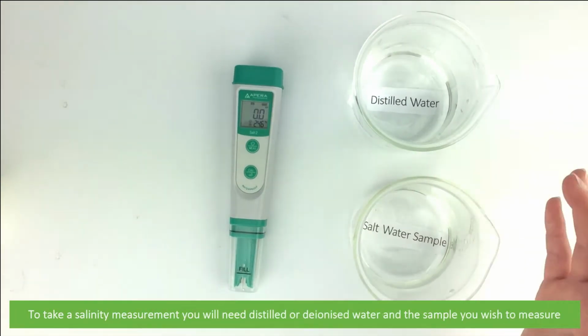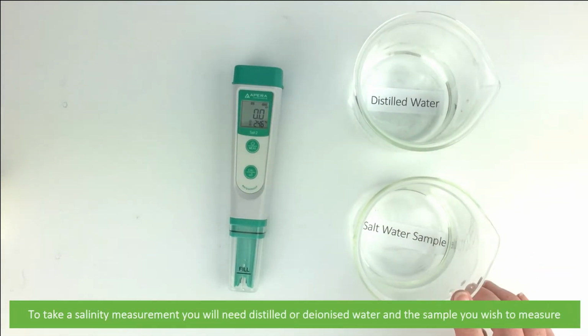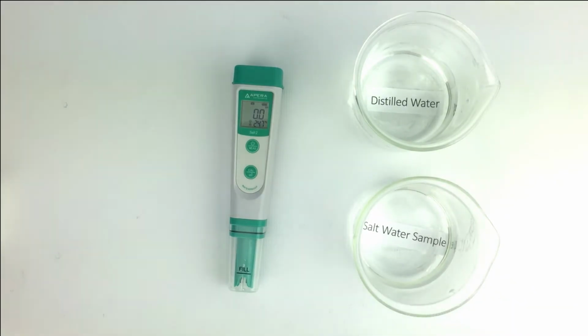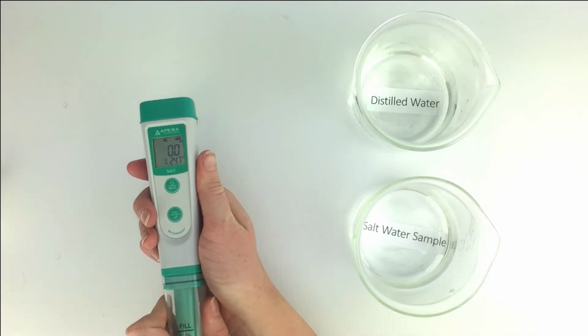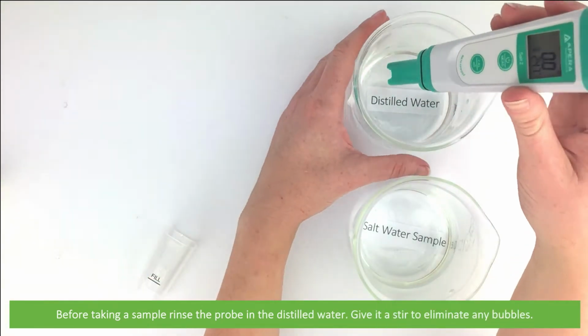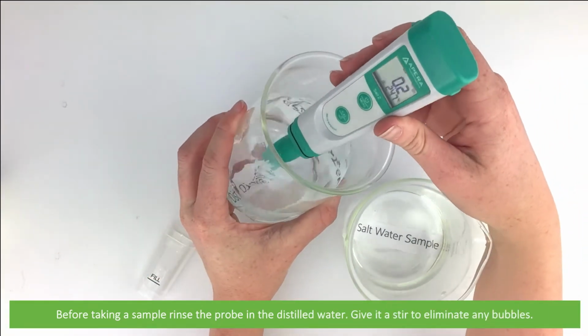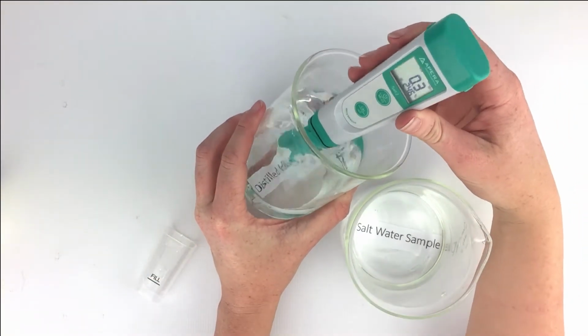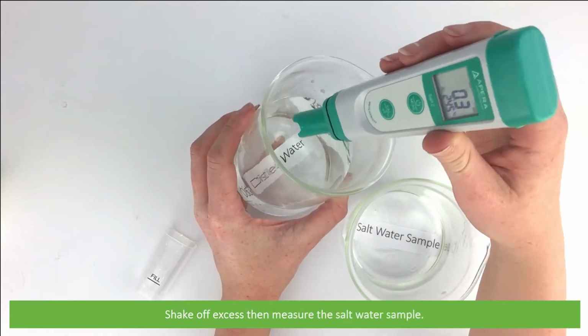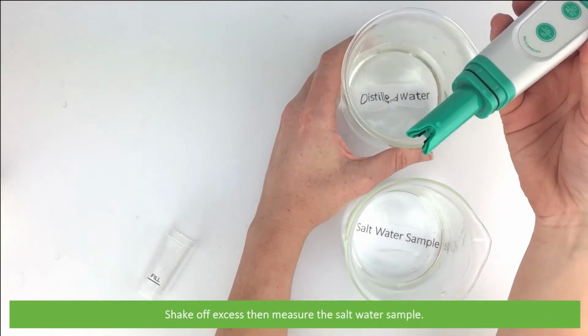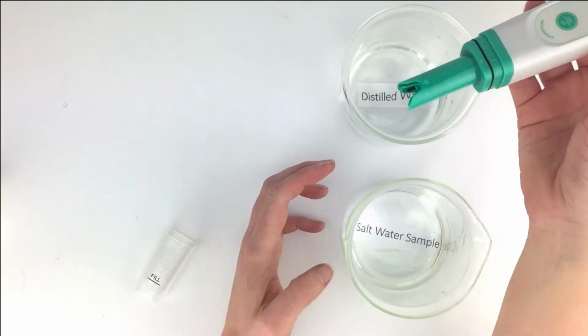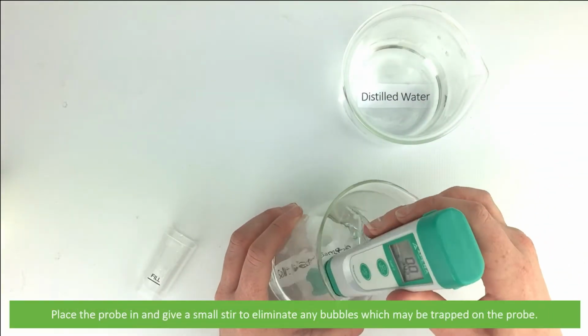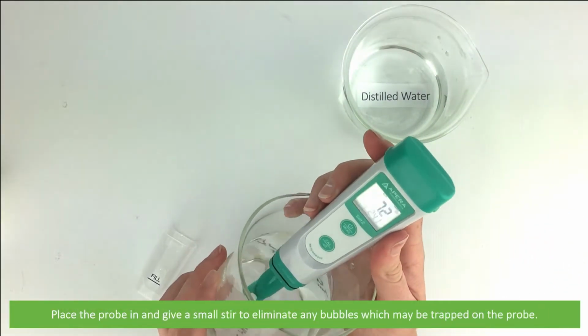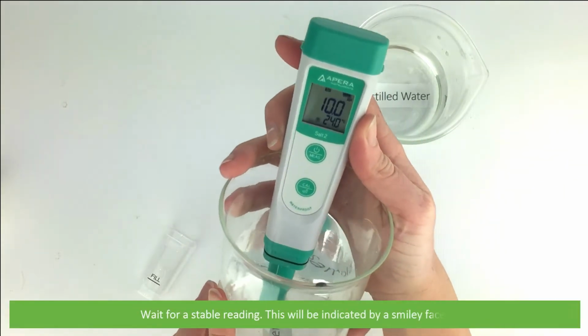To take a salinity measurement, you will need distilled or deionized water and the sample you wish to measure. Before taking the sample, rinse the probe in the distilled water, give it a stir to eliminate any bubbles. Shake off the excess and then measure the saltwater sample. Place the probe in and give it a small stir to eliminate any bubbles which may be trapped in the probe. Wait for a stable reading.